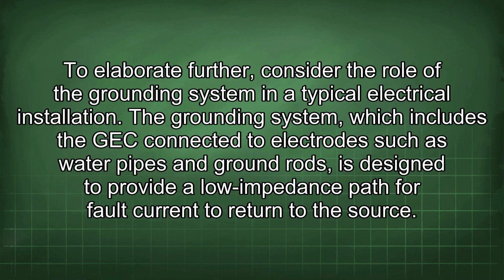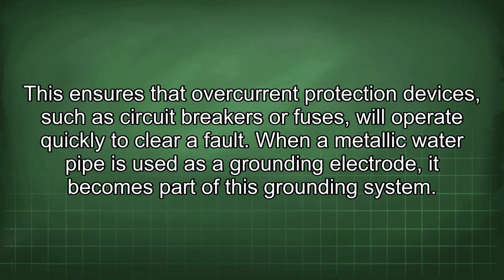To elaborate further, consider the role of the grounding system in a typical electrical installation. The grounding system, which includes the GEC connected to electrodes such as water pipes and ground rods, is designed to provide a low impedance path for fault current to return to the source. This ensures that overcurrent protection devices, such as circuit breakers or fuses, will operate quickly to clear a fault.